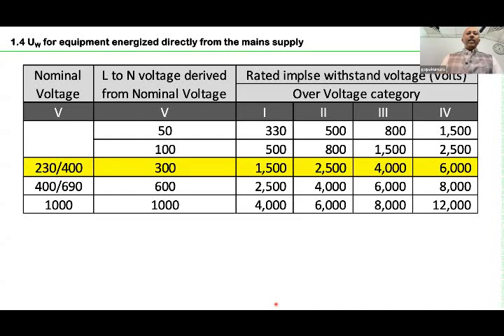For low voltage, the equipment manufacturer is supposed to categorize that particular equipment. There are 4 overvoltage categories: 1, 2, 3, 4. Category 1 means an electrical device which can withstand only 1.5 kV, category 2 means 2.5 kV, 3 means 4 kV, and 4 means 6 kV. So to select a surge protective device, the first parameter you should understand is the impulse voltage withstanding capacity of your electrical installation. Because imagine your withstanding capacity is 1.5 kV and you put in an SPD clamping at 4 kV. There is no use, because the electrical device will fail.